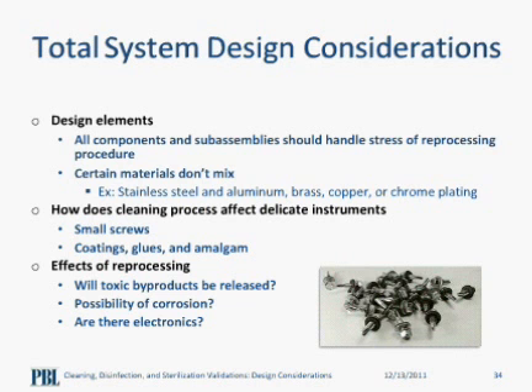When we say total system design considerations, we are looking at the whole system and how reprocessing affects the overall device. The design elements such as the components, subassemblies, and the complete device itself should be evaluated for how they are affected by the stress imposed by cleaning, disinfection, and sterilization procedures, and other stresses from mechanical, electrical, and environmental sources. All of these conditions should be evaluated in terms of any potential effect on the device's compatibility with other devices in the intended operating system. For example, stainless steel should not be mixed with aluminum, brass, copper, or chrome-plated devices, as it can cause an electrochemical reaction.